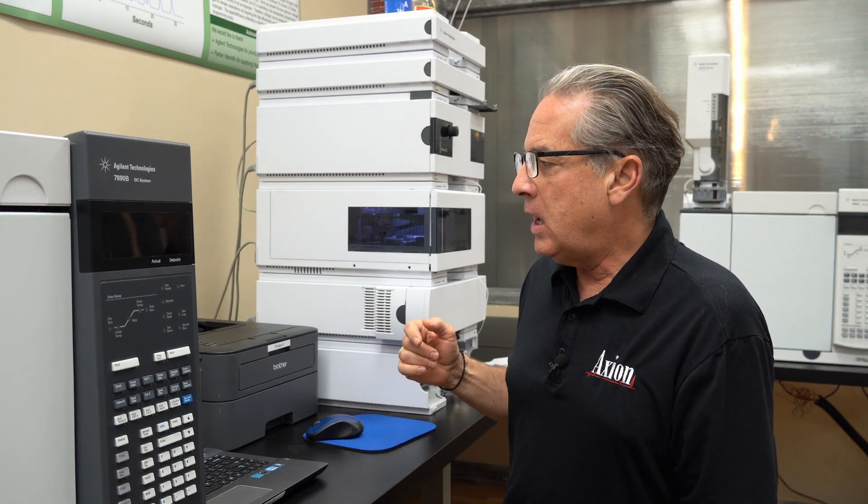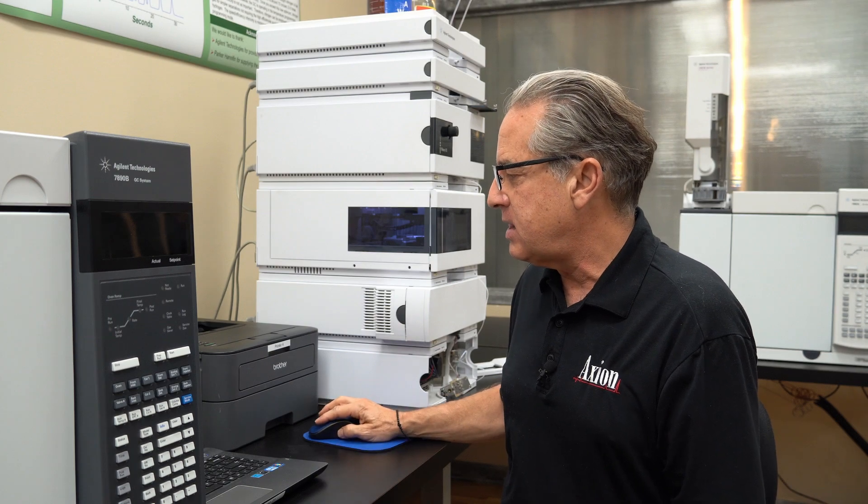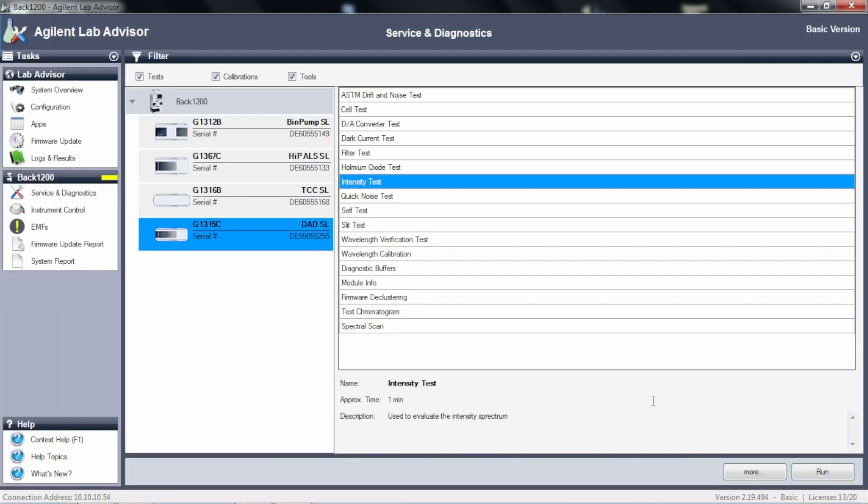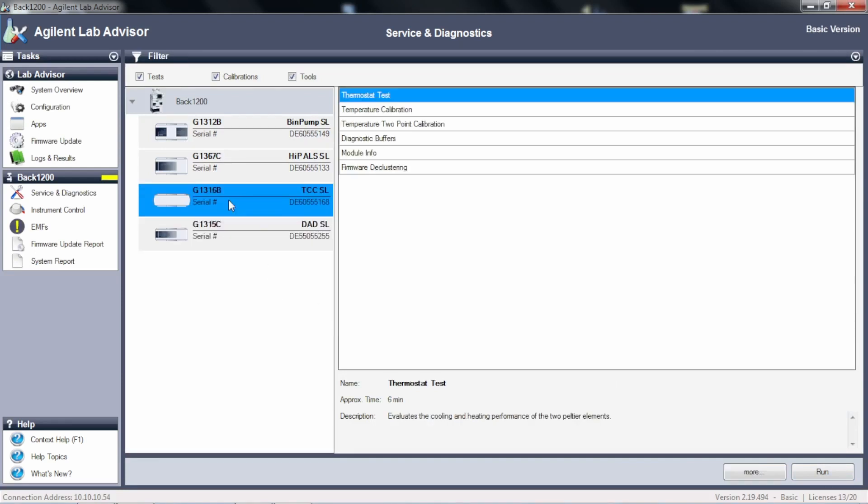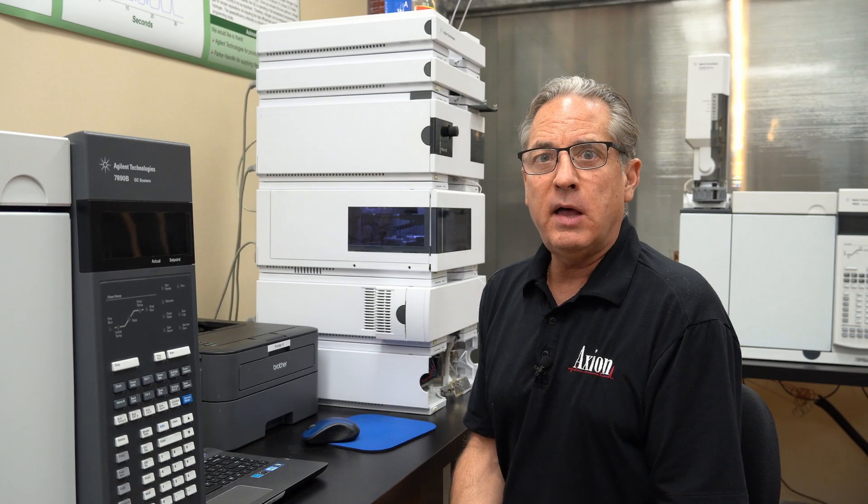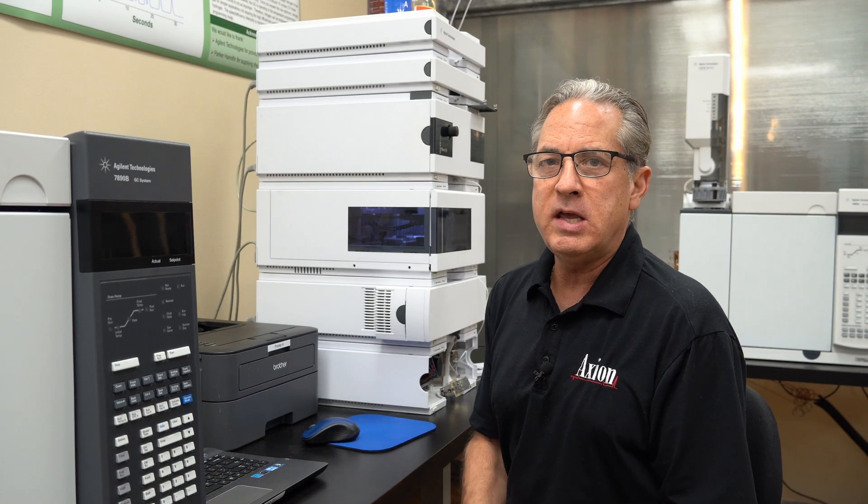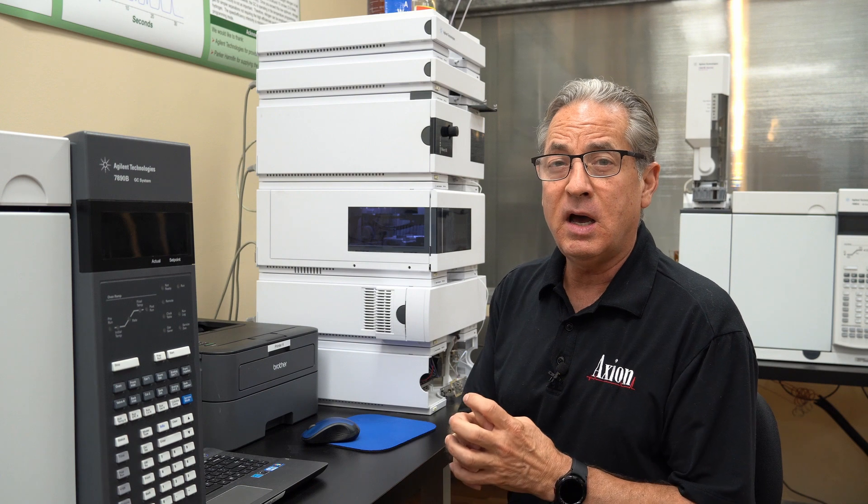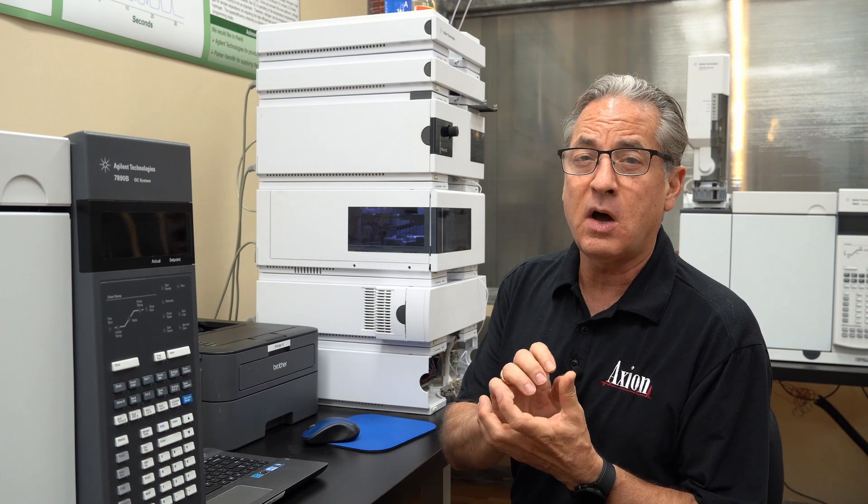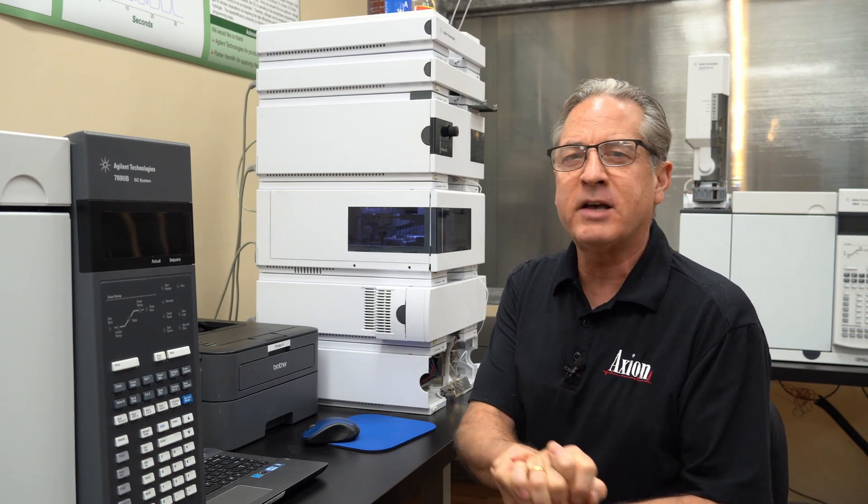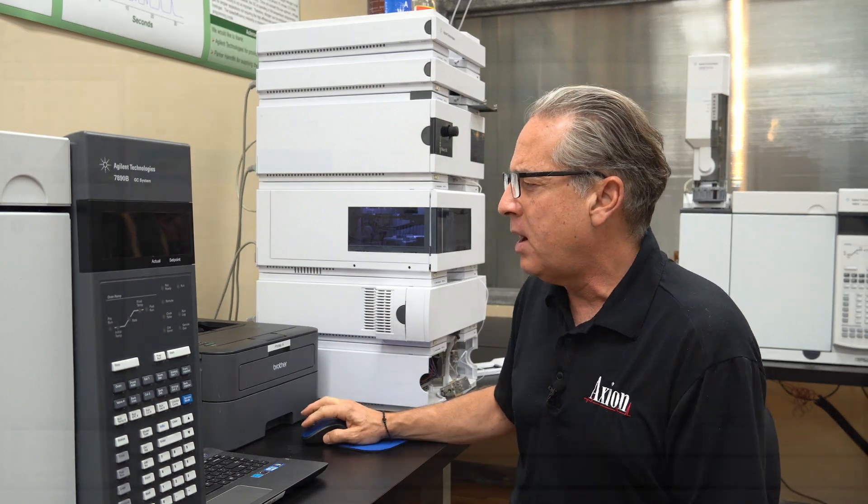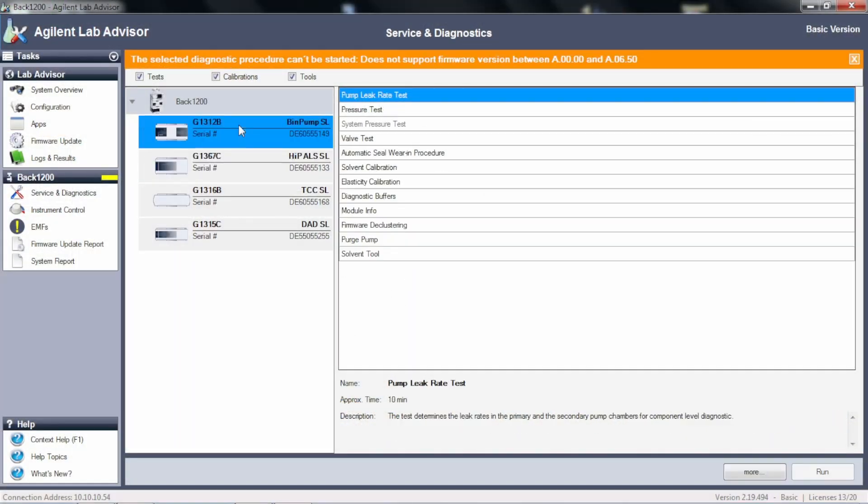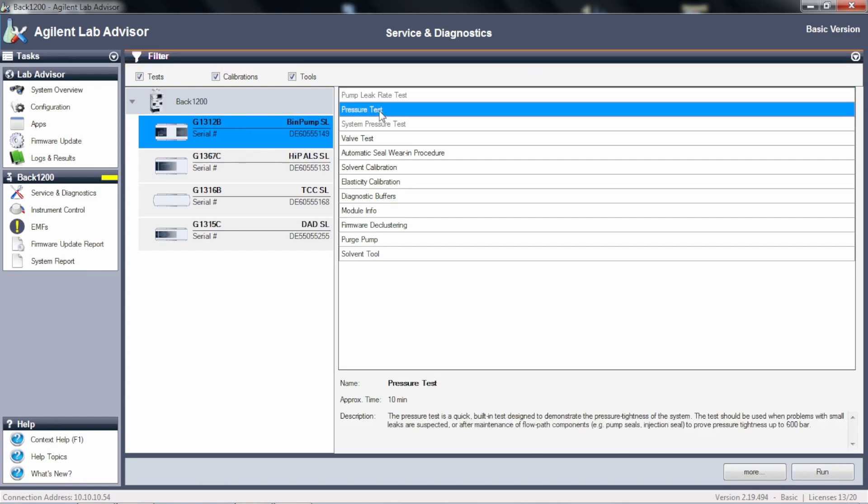So there's a whole host of tests that are available in here for you. You just take a quick look at the diode array. You have all kinds of tests that you could run. With each component, they have their own tests. Even the column thermostat has a test. It heats and cools and it knows how long it should take. We can do some diagnostic tests with the auto sampler as well. The neat thing about the auto sampler is we can do some specific tests on the pressure in terms of the main pass versus the bypass. And then the pump usually has quite a few tests. Things like the pressure tests, what it essentially does is pressurize the pump head and then shuts off the pump to see if the pressure maintains.